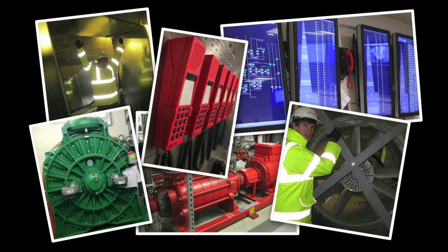All of this has a profound impact on the design of the building services. The use of lifts during a potential fire means that the shafts must be pressurized to prevent the ingress of smoke, and pressurized refuges must also be provided to give people a safe place to wait as the lifts shuttle people to safety. The lift motors work hard and give off a lot of heat, and so the lift motor rooms need a cooling system that can keep running in the event of an emergency.